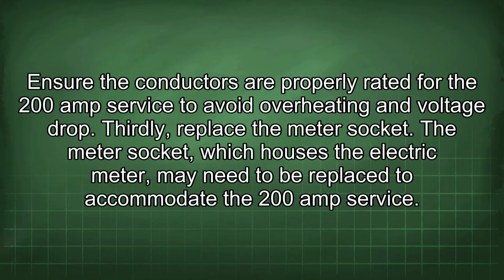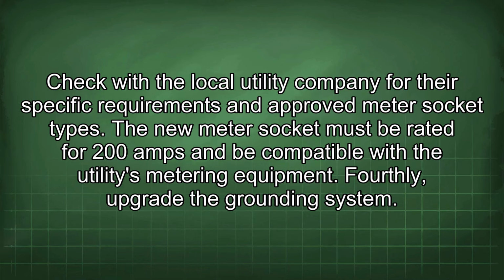Thirdly, replace the meter socket. The meter socket, which houses the electric meter, may need to be replaced to accommodate the 200 amp service. Check with the local utility company for their specific requirements and approved meter socket types. The new meter socket must be rated for 200 amps and be compatible with the utility's metering equipment.